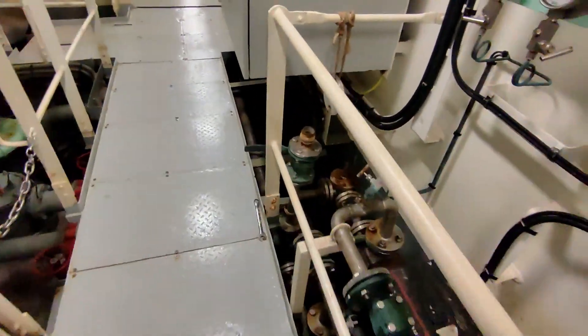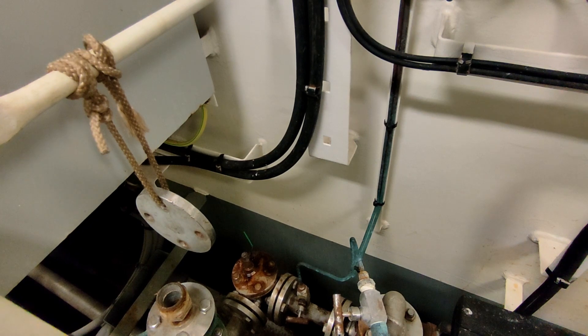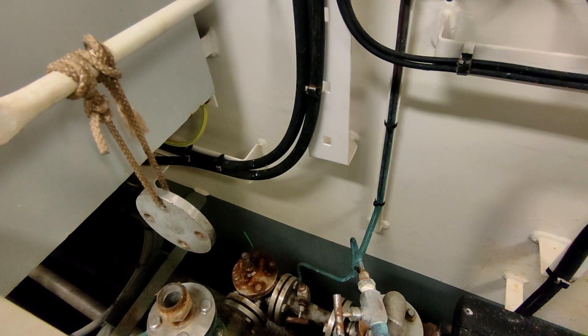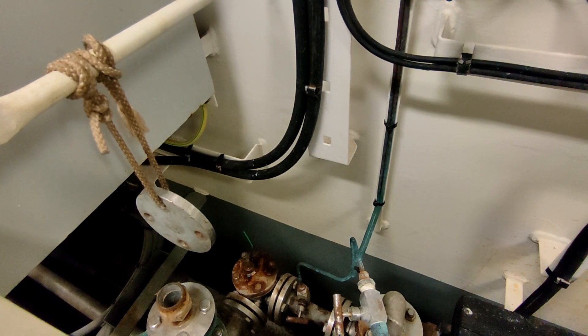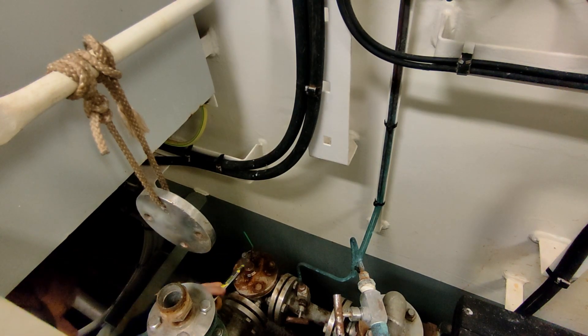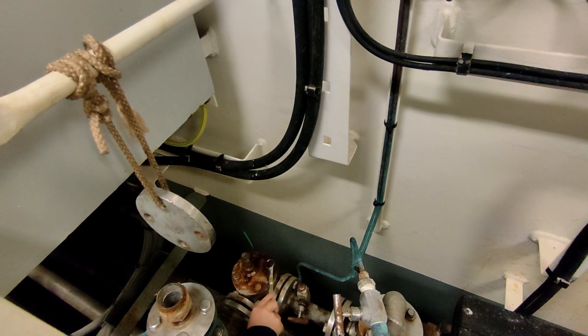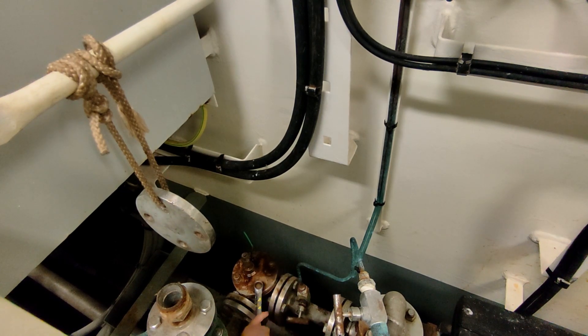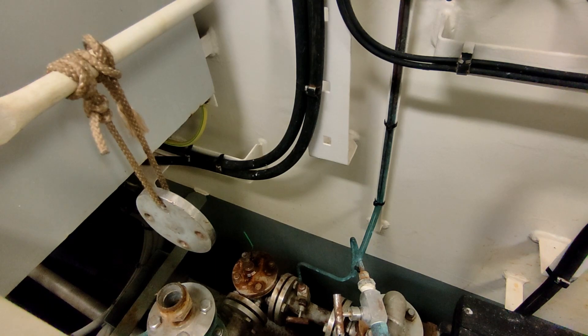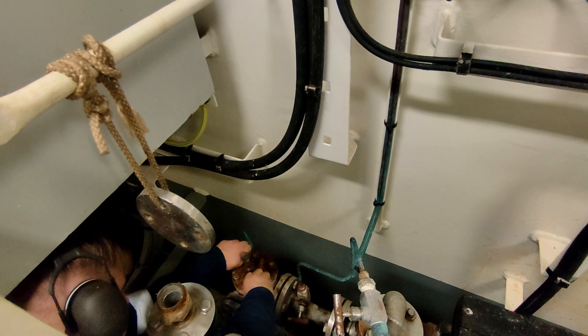So that's that done. Whilst they're draining, I'm going to clean the coarse filter over here. So to open this filter up, I've got four M12 bolts. I'm just going to crack them off. And these don't have to be tightened excessively tight. There's an O-ring underneath, and as long as that's sealing, then really that's tight enough. So that's then cracked off, get these out by hand now.